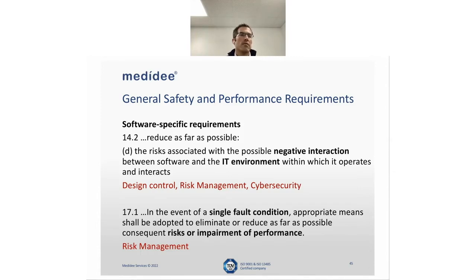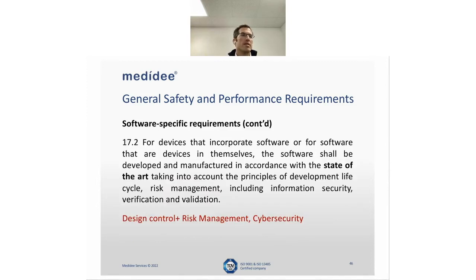Another requirement: in the event of a single fault condition, appropriate means shall be adopted to eliminate or reduce as far as possible consequent risks or impairment of performance. So typically you need to consider, not only for software here, if your device is making a single fault condition, so the primary fault with your device, what are the consequences and how do you handle them? For devices that incorporate software or for software that are devices in themselves, the software shall be developed and manufactured in accordance with the state of the art, taking into account the principles of development lifecycle, risk management, including information security, verification, and validation.